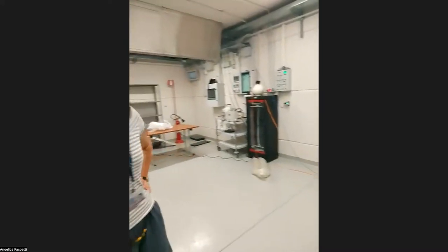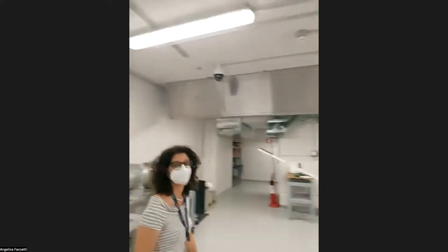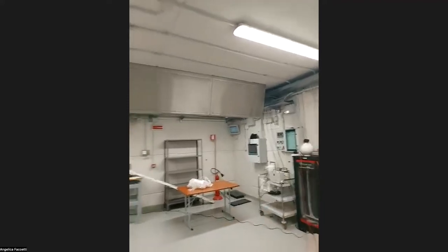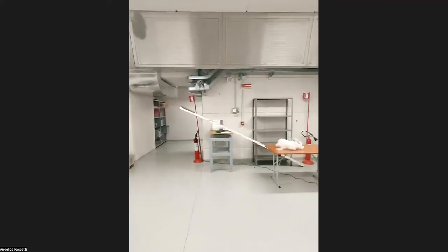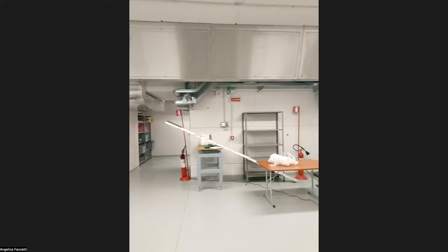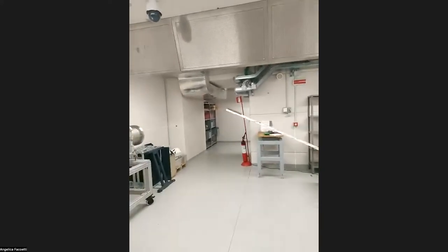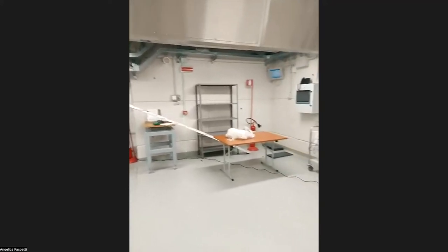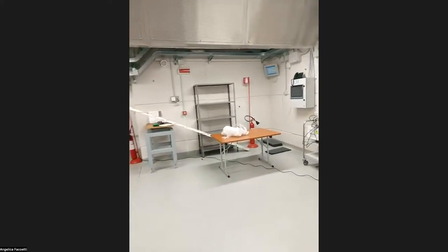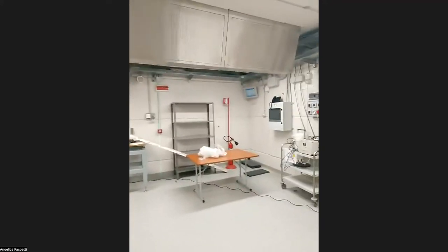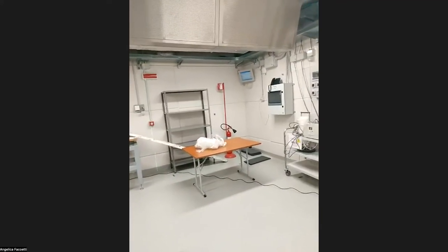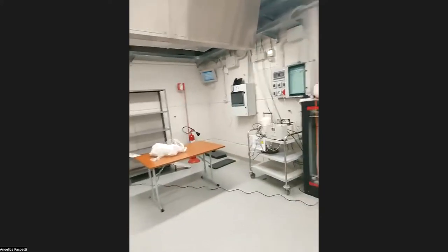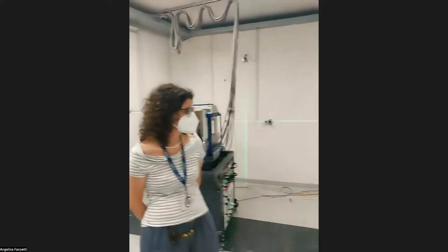And what else? Well, the big thing here on the roof is the air diffusion, because we have to change the air inside this room 15 times per hour. If you have this flow on a small tube, then the velocity of the air is large. It would perturb the experiments. So a large diffuser helps to reduce the airspeed. And what else? That's basically it.